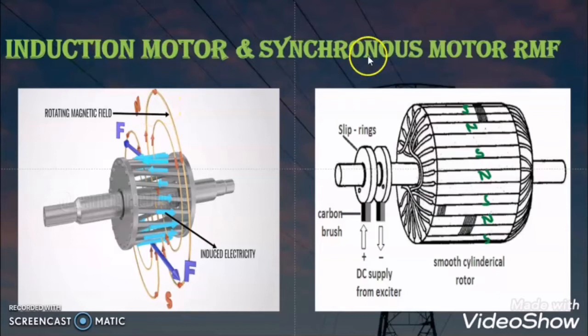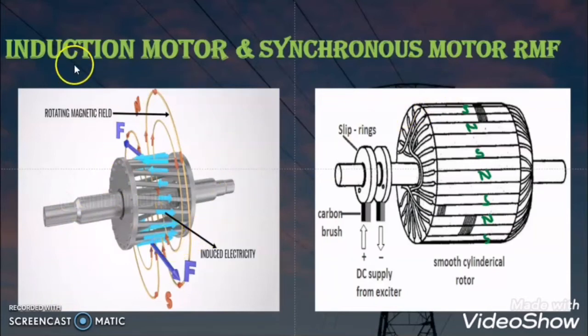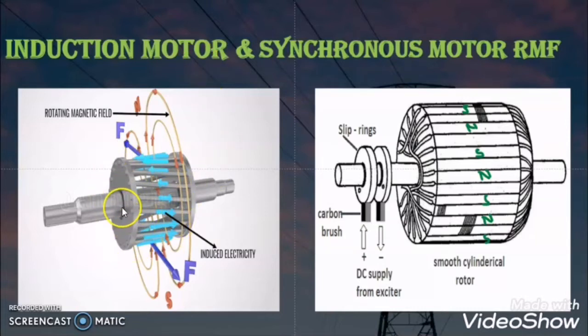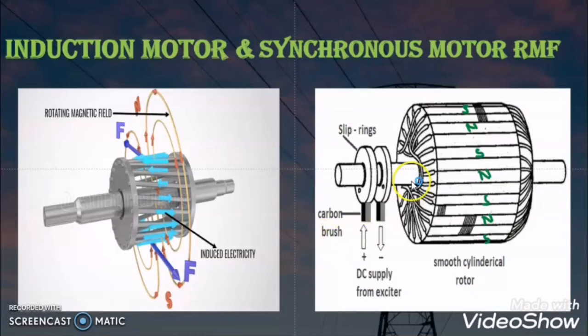The difference between induction motor and synchronous motor lies in the fact that the rotor construction of these two motors are quite different. In case of squirrel cage induction motor, there is a metal bar which is short circuited by the end ring. But in case of synchronous motor, the rotor has windings which are not short circuited but connected with the slip ring and carbon brush arrangement.